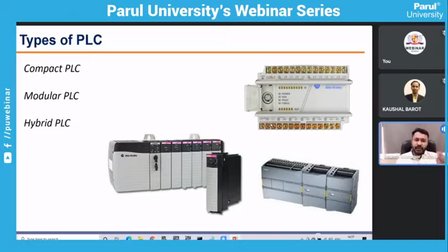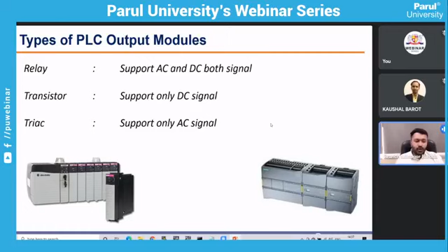Then any PLC has an output module. That has 3 types of output module. One will be relay, second will be transistor, and the third triac. So what is the relay? It will give you output in AC and DC both. In transistor, you will get only DC type output, and in triac you will get only AC type output. So whatever application you have, whatever output type you have in your devices, accordingly you have to choose your PLC.